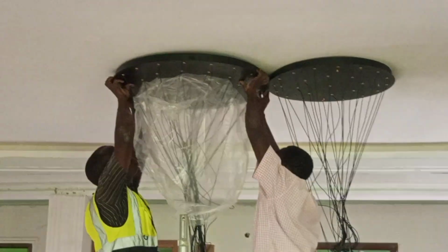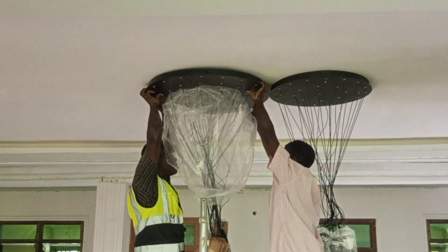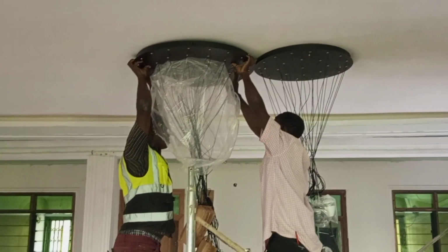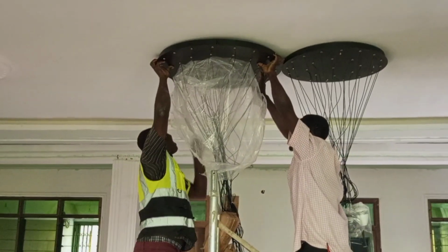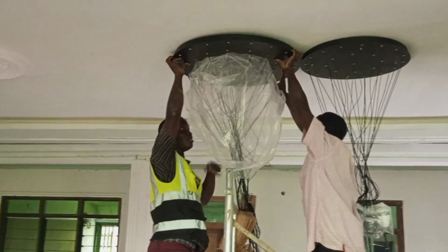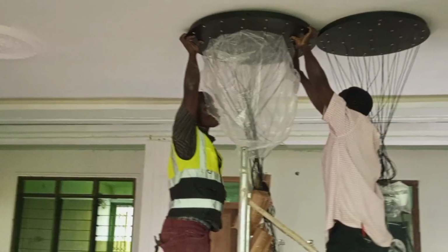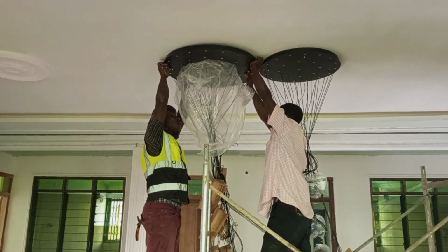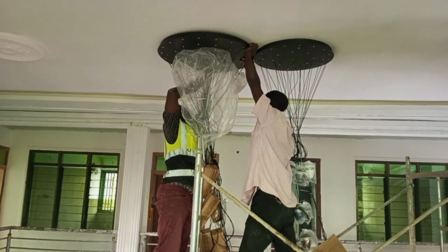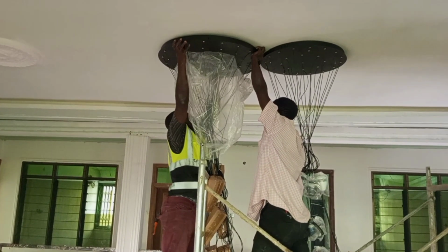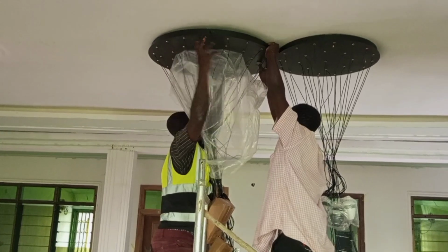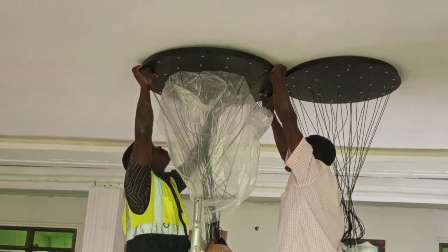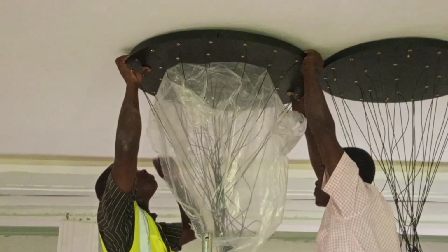So, in a normal simple wiring where you use one light in every room, you can combine like 10 rooms, and one 6 amp breaker will be enough for all the 10 rooms. But in the example I have just given, where you are using so many lamps in one room, combining 10 rooms on one breaker may not be safe for your cables and may also be too much for the breaker to bear. So, even in the case where there is no fault, your breaker can intermittently trip, and we don't need that.